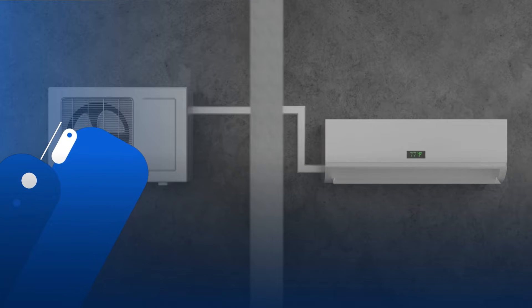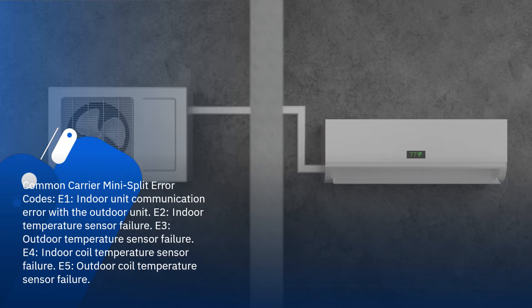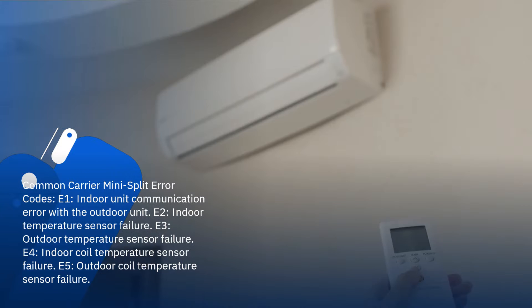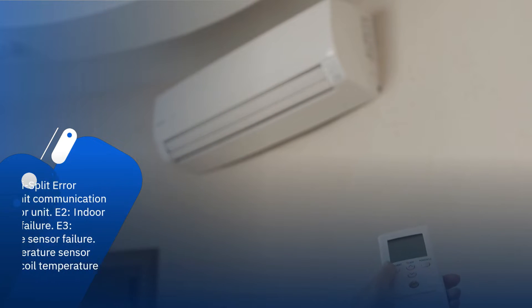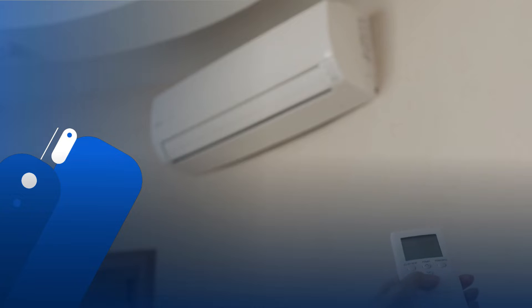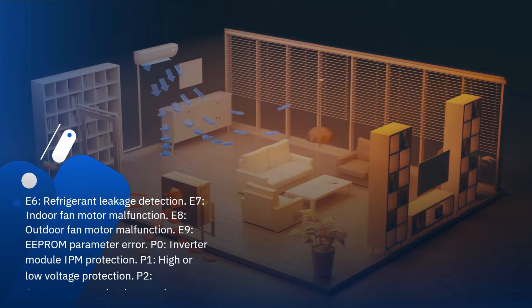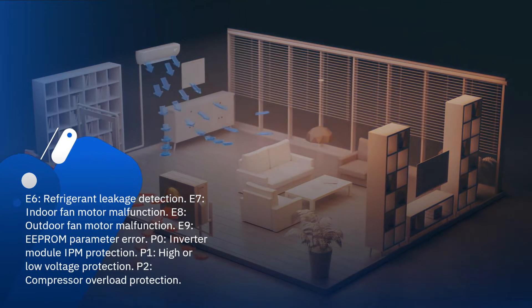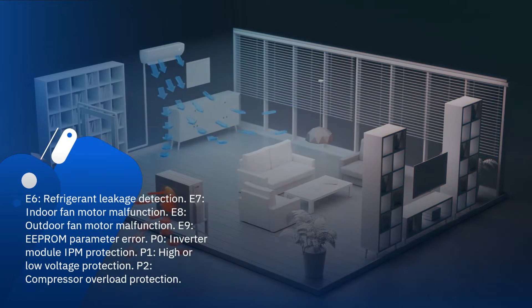Common Carrier Mini-Split Error Codes: E1 — Indoor Unit Communication Error with the Outdoor Unit; E2 — Indoor Temperature Sensor Failure; E3 — Outdoor Temperature Sensor Failure; E4 — Indoor Coil Temperature Sensor Failure; E5 — Outdoor Coil Temperature Sensor Failure; E6 — Refrigerant Leakage Detection; E7 — Indoor Fan Motor Malfunction; E8 — Outdoor Fan Motor Malfunction.